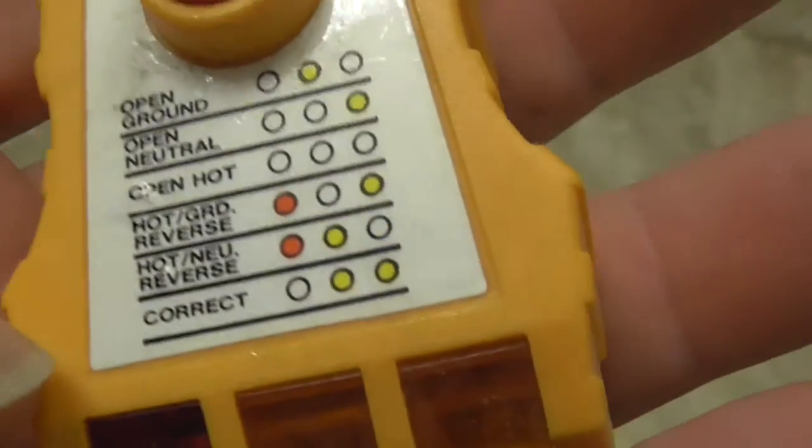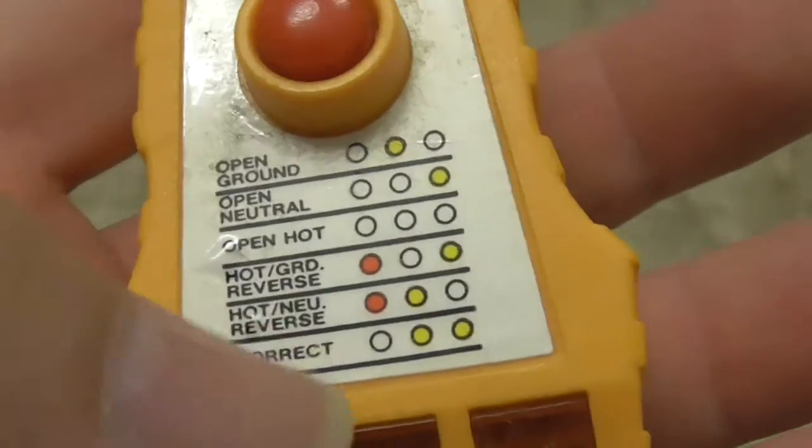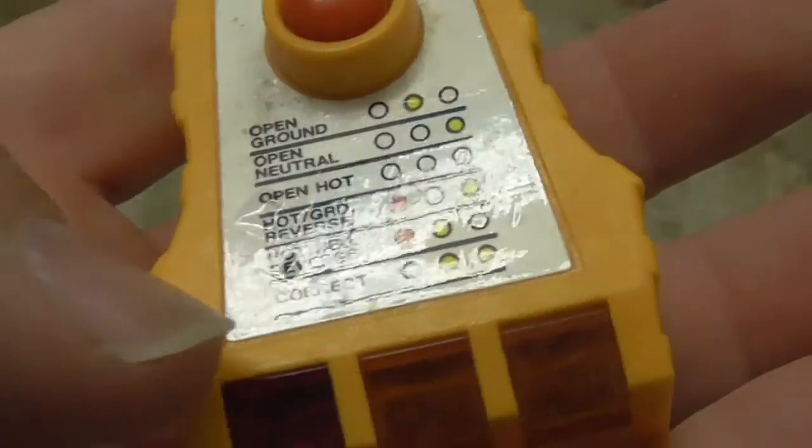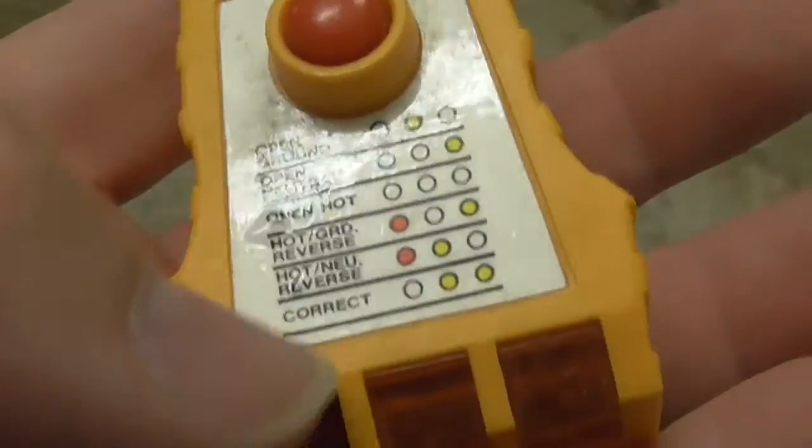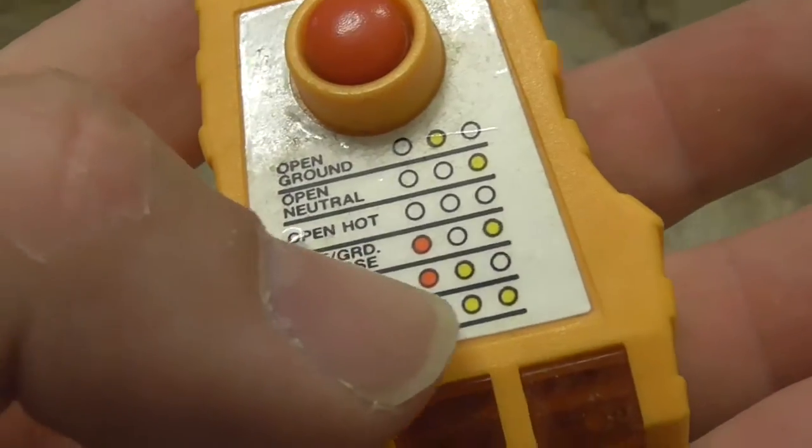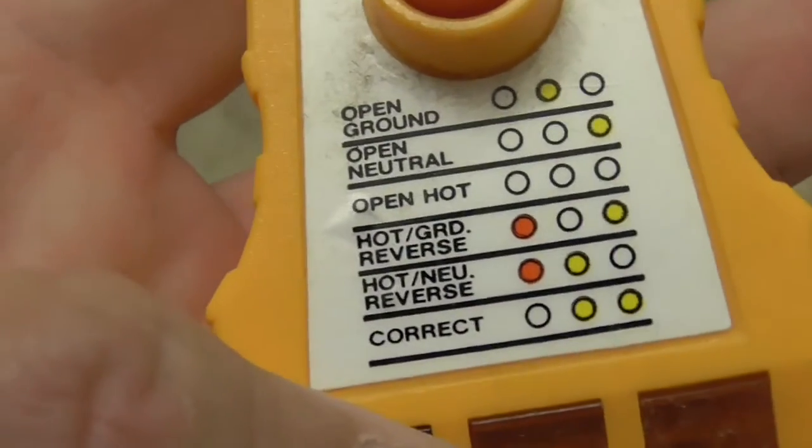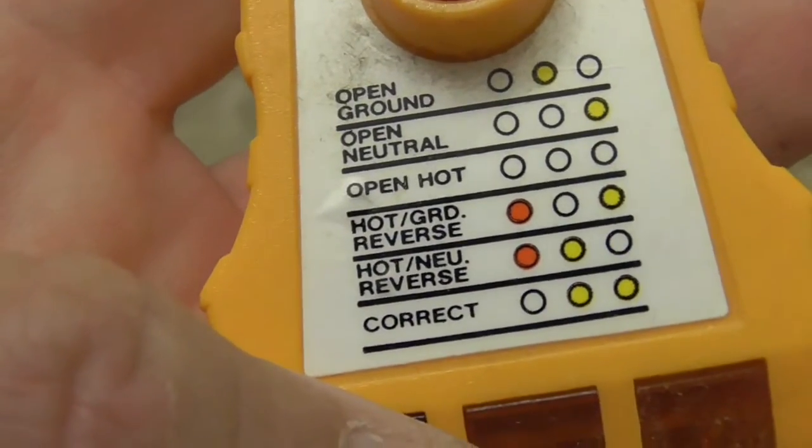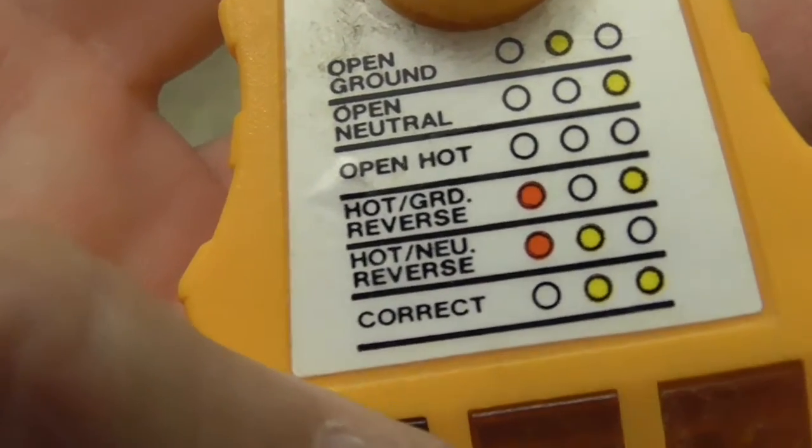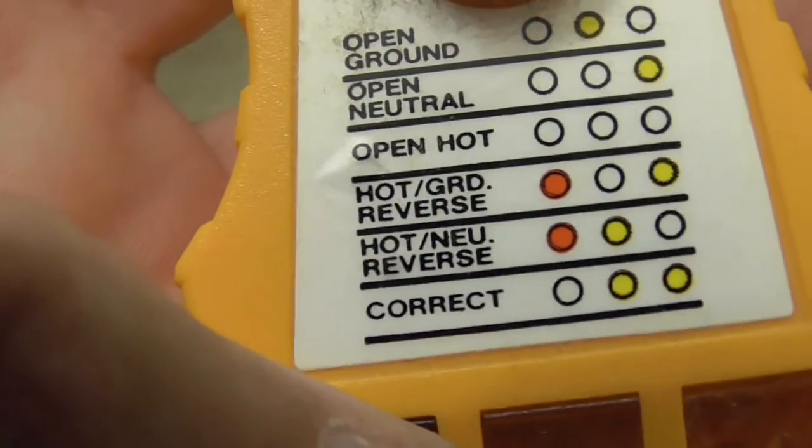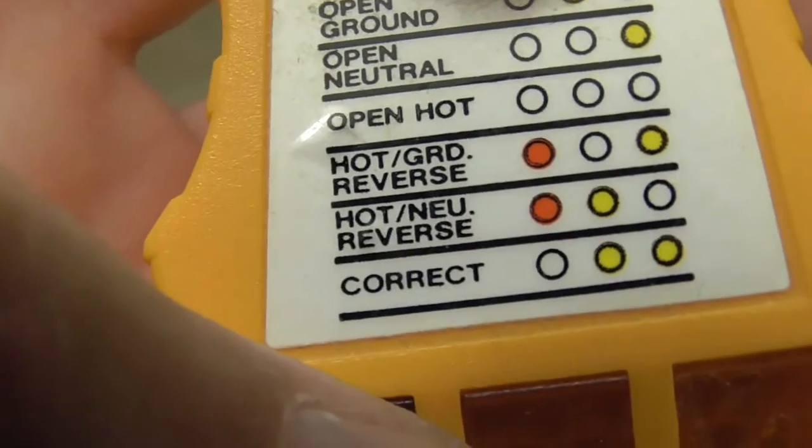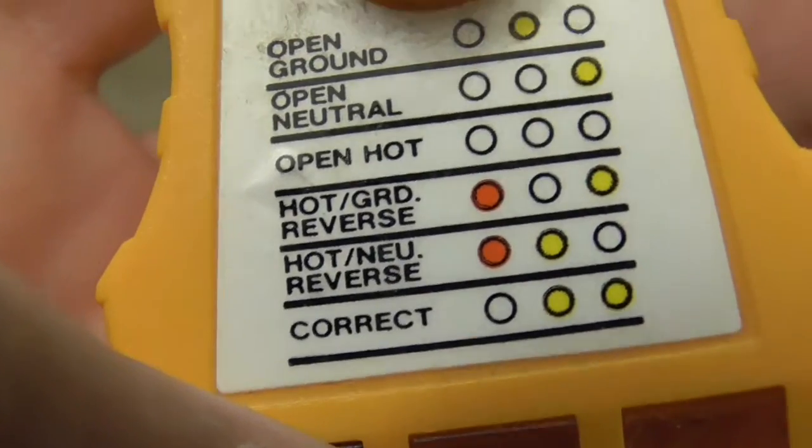So let's unplug it and look and see what that is. Red, I'll turn this upside down, so it's red, yellow, and nothing. What does it say? It says hot and neutral are reversed.